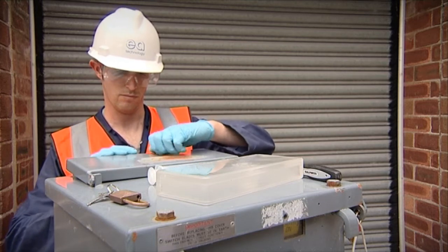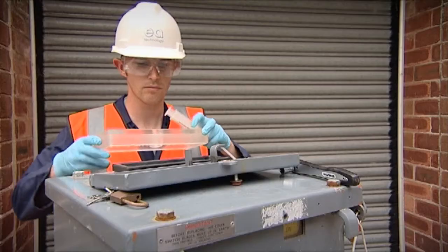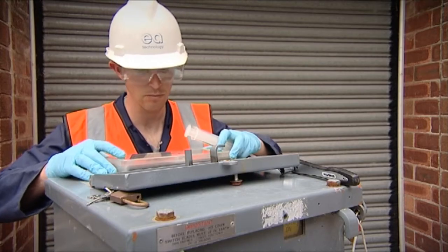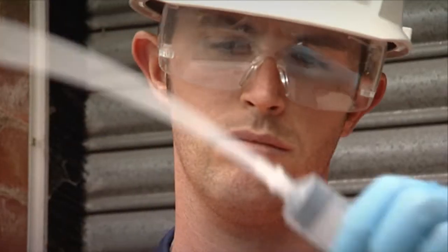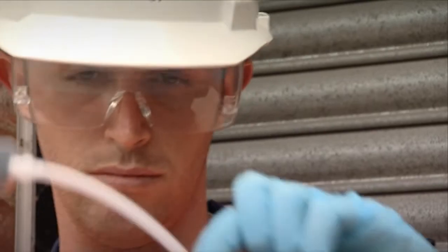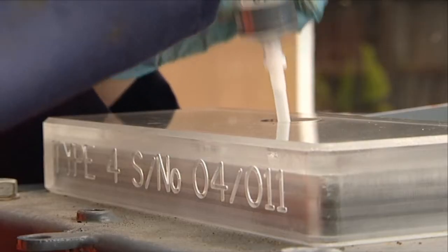The sampling equipment is essentially in two parts: a reusable cover plate that sits over the top of the access cover, and a disposable sampling syringe. The cover plate is specially designed for each type of switchgear it is used on. It effectively sits over the test access probe and blanks off the main tank.